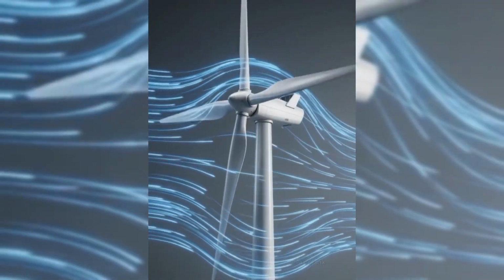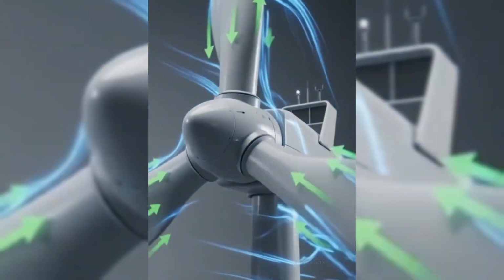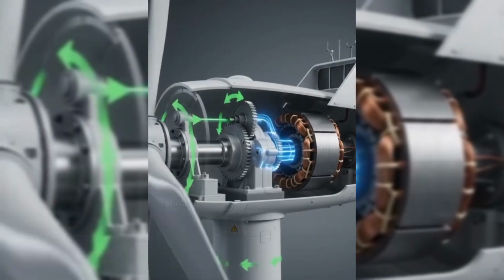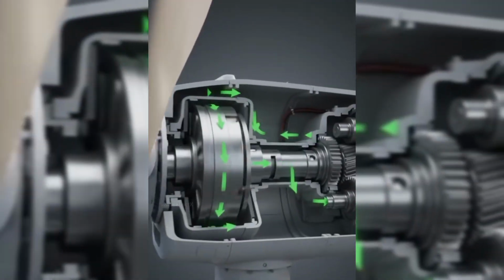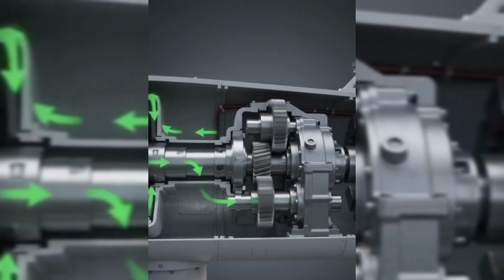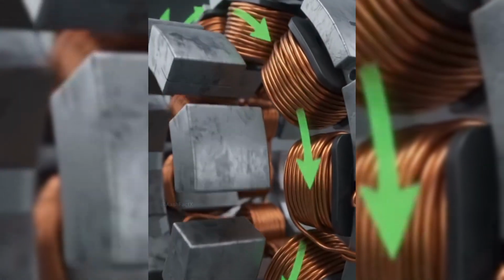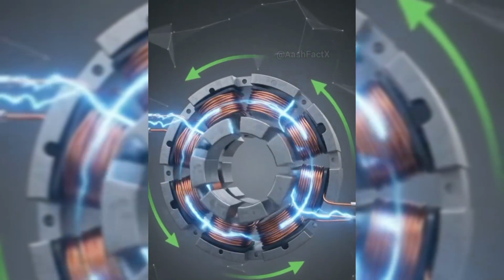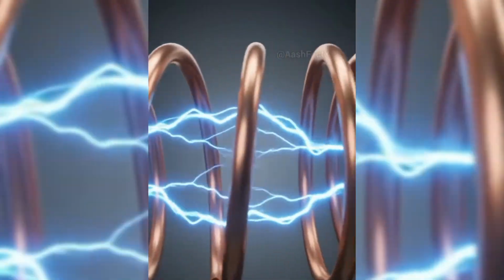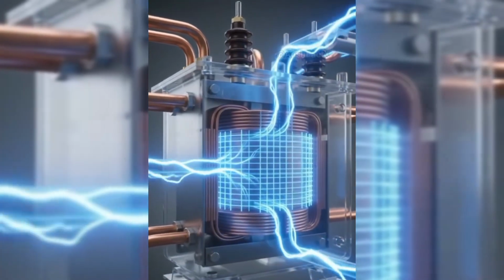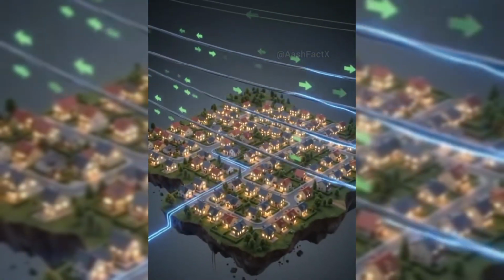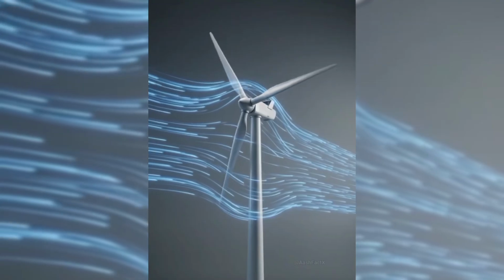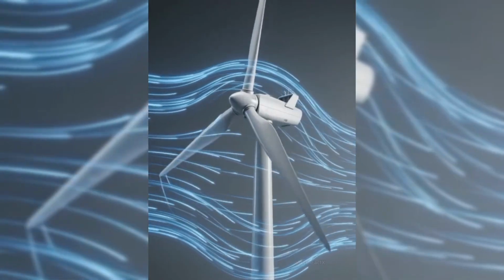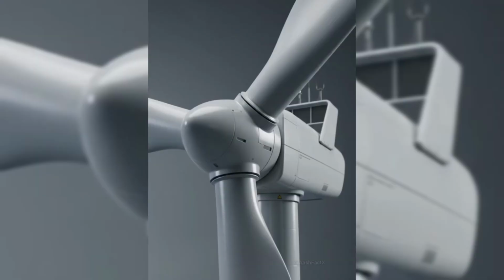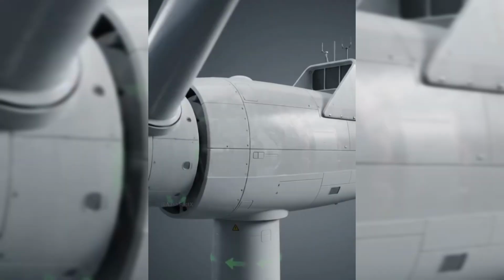Every single phase of this process operates seamlessly under the continuous supervision of advanced automated sensors and computerized control systems. Wind vanes and anemometers mounted on the turbine continuously monitor the direction and speed of the wind. If the wind direction shifts, small yaw motors rotate the entire nacelle to face directly into the oncoming breeze to maximize power capture. If the wind becomes dangerously strong during severe storms, computer systems automatically pivot the blades out of the wind to stop rotation, preventing structural damage to the machinery.